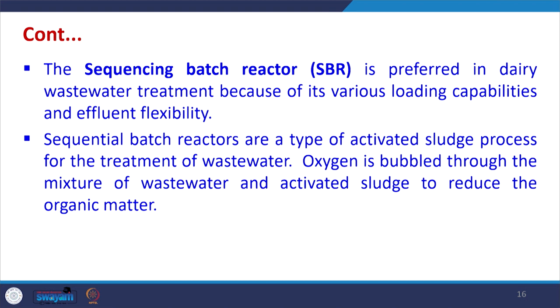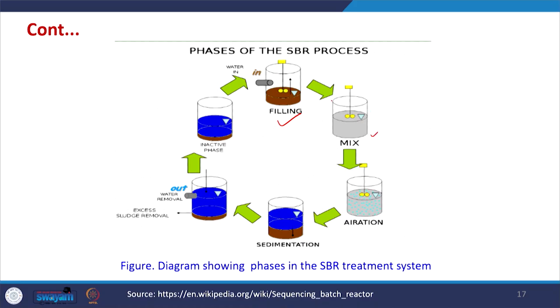Sequential batch reactors are a type of activated sludge process for wastewater treatment, where oxygen is bubbled through the mixture of wastewater and activated sludge to reduce organic matter. The SBR process includes a fill phase, a mixing phase where water enters, followed by aeration, then sedimentation where the sludge settles. After treatment the treated wastewater is removed and the excess sludge is also removed, followed by an idle phase depending on retention times.